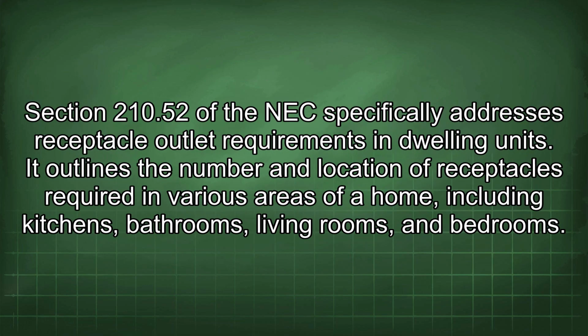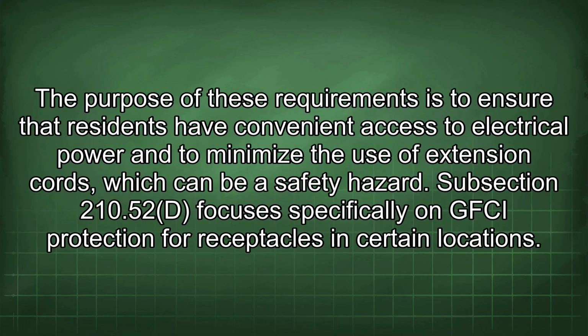hazards. Section 210.52 of the NEC specifically addresses receptacle outlet requirements in dwelling units. It outlines the number and location of receptacles required in various areas of a home, including kitchens, bathrooms, living rooms, and bedrooms. The purpose of these requirements is to ensure that residents have convenient access to electrical power and to minimize the use of extension cords, which can be a safety hazard.